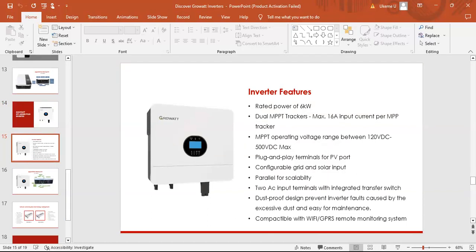This is to say that one of the MPPT trackers can carry up to 16 amps of solar arrays. So when you put the two MPPT trackers together, you should be able to have up to 32 amps from your PV array coming to the inverter, which is a lot. MPPT operating voltage range between 120 VDC to 500 VDC. So this one gives maximum allowance compared to the former, which is the SPF 5000 ES. So this one, you can have operating voltage of up to 500 VDC from your solar array.